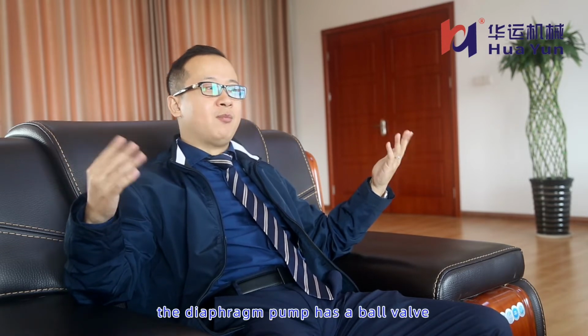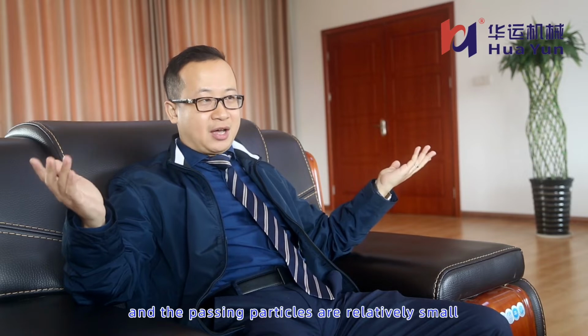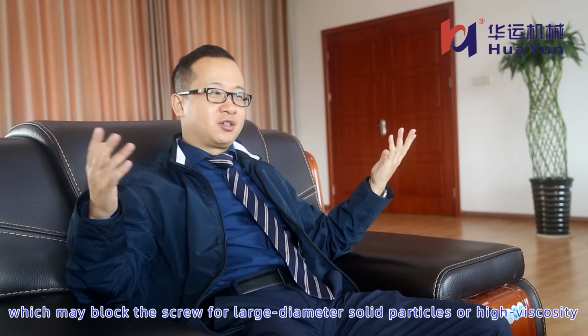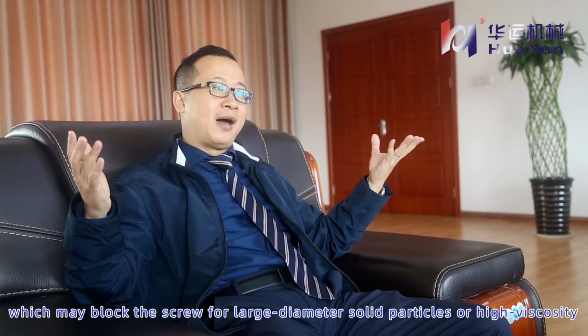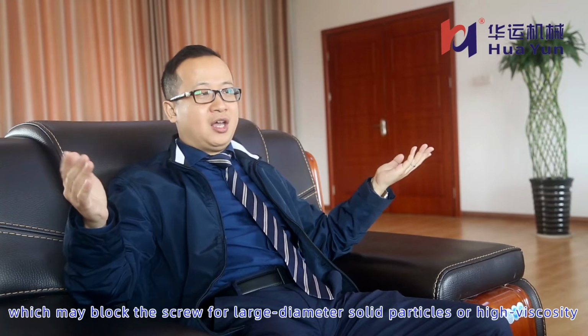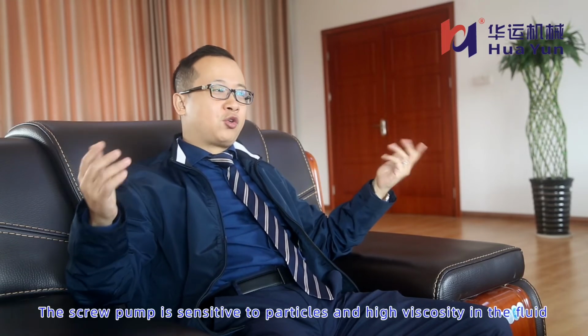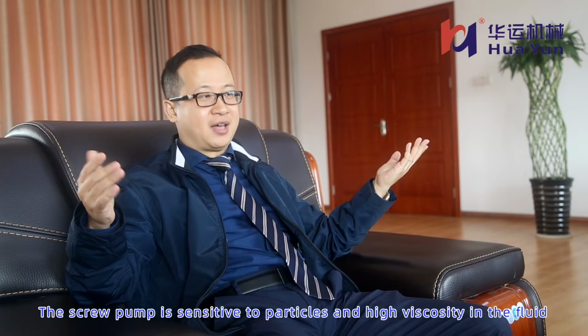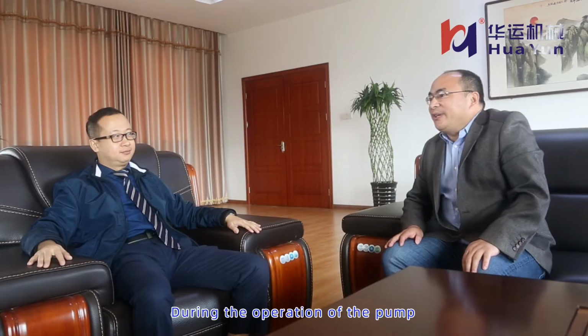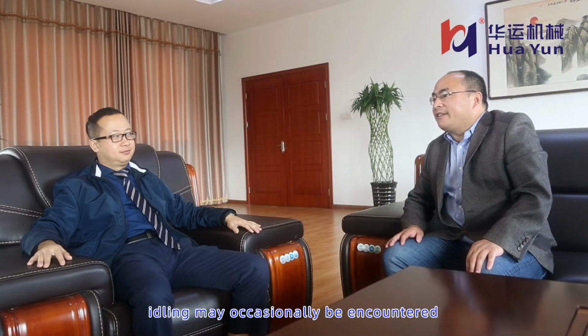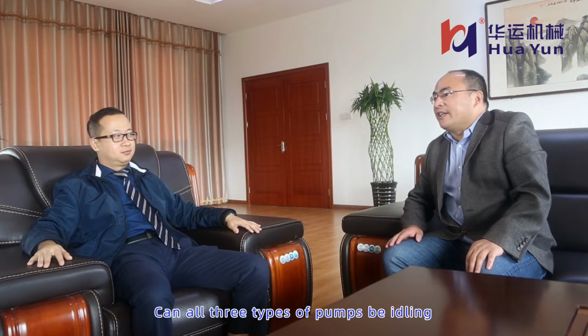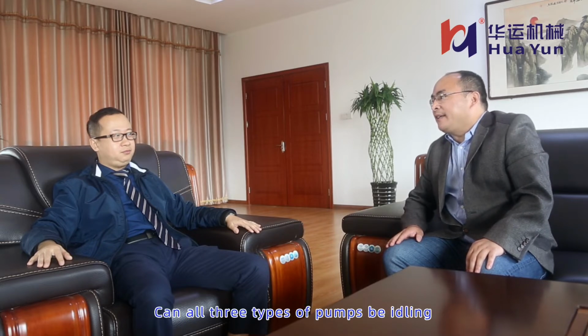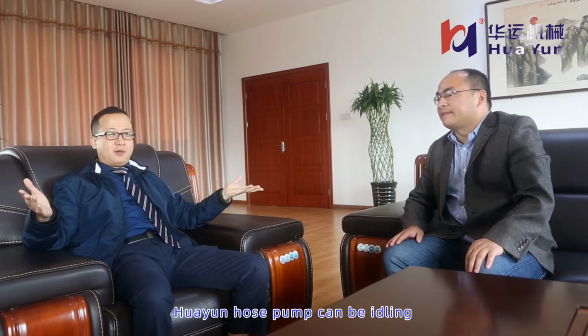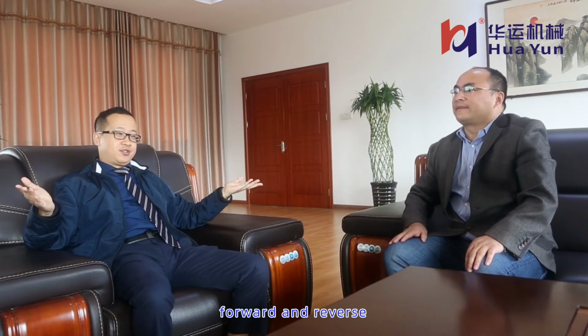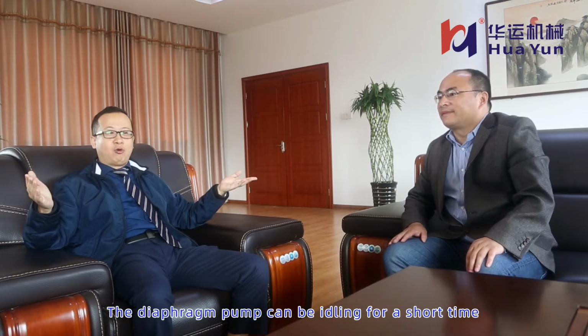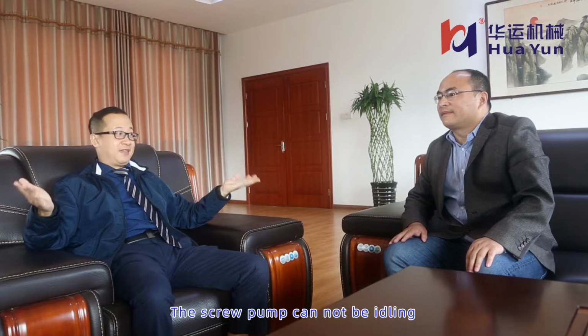The diaphragm pump has a ball valve and the passing particles are relatively small, and large solid particles or high viscosity, high concentration materials may block it. The screw pump is sensitive to particles and high viscosity in the fluid. During the operation of the pump, dry running may be encountered. Can all three types of pumps run dry? The Huayun hose pump can run dry, forward and reverse. The diaphragm pump can run dry for a short time. The screw pump cannot run dry.